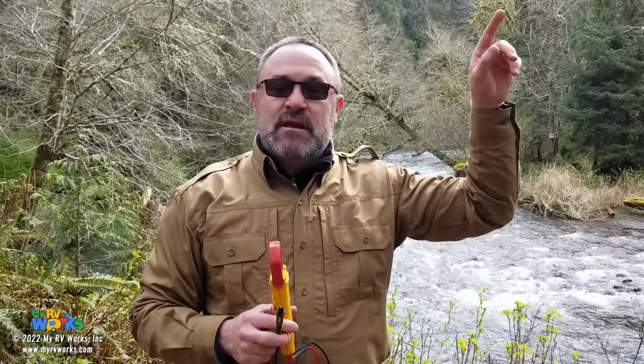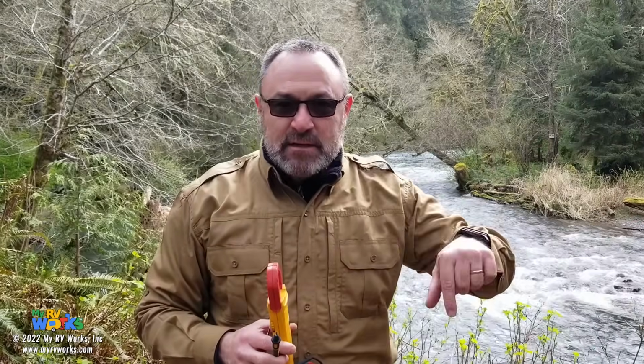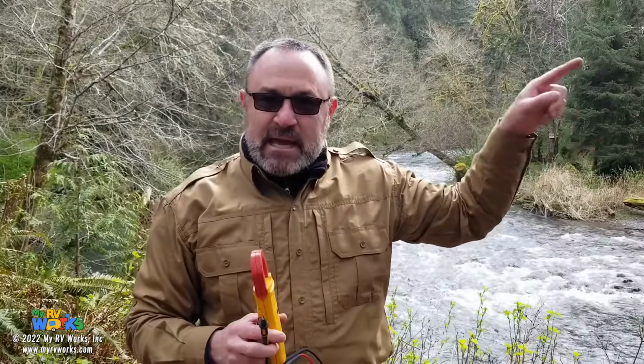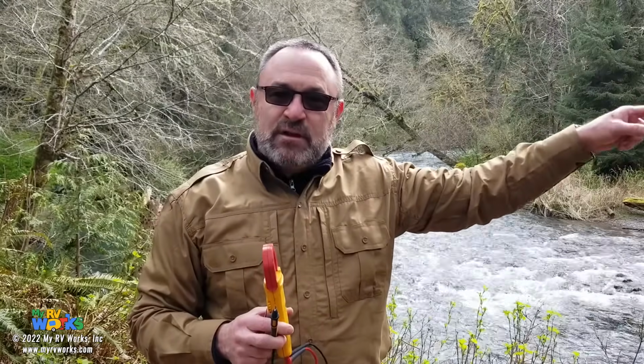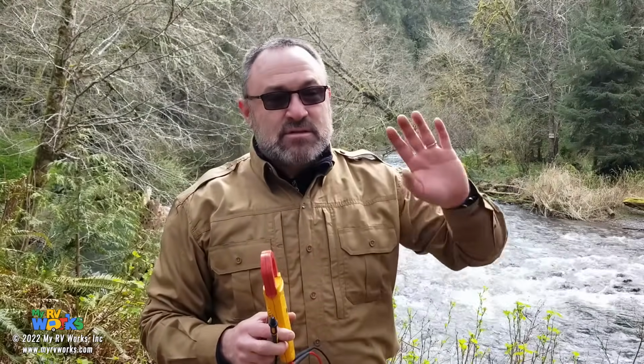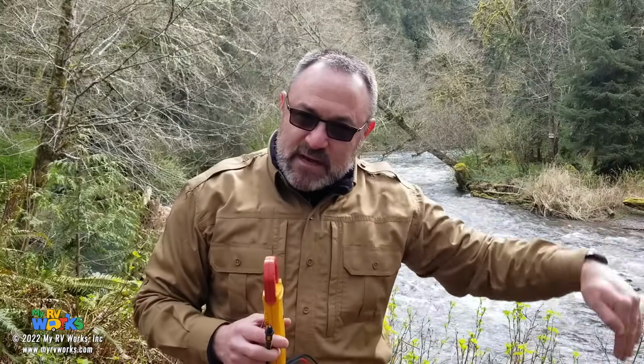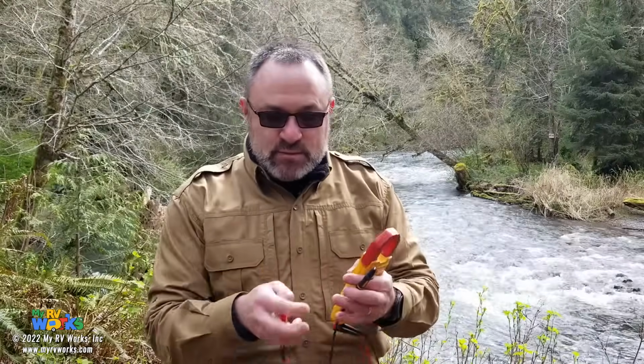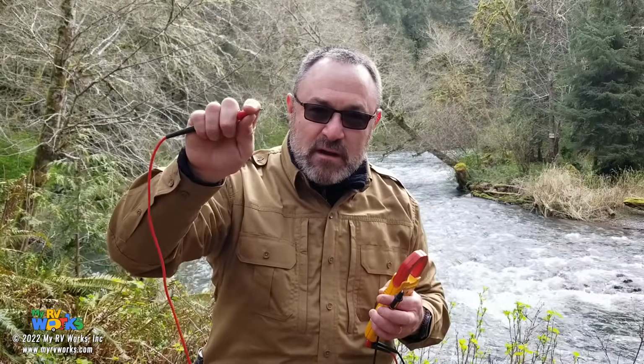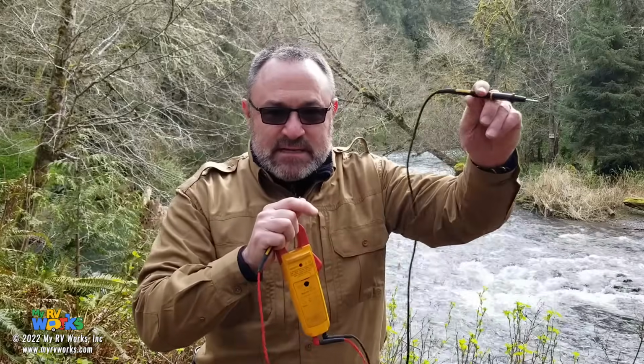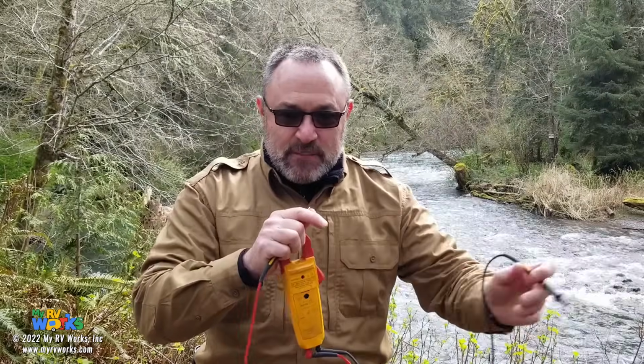In a house, they are bonded. In an RV, they are not bonded. Well, where does the bond take place? It takes place back at the point of origin of your electricity - if it's your house, at your breaker box where they drive that ground rod into the ground 6 feet. That's where the ground and neutral get bonded, not in your RV. So test this on the black wire you disconnected, then test it on the neutral, test it on the ground.